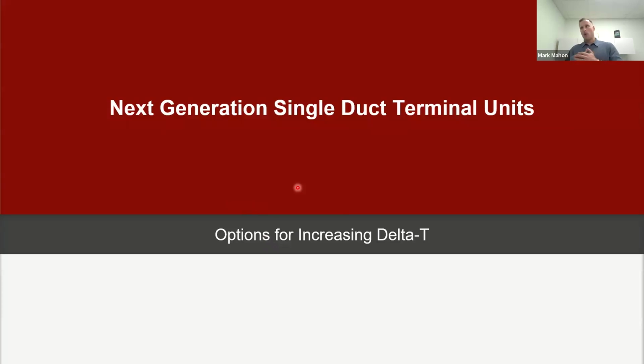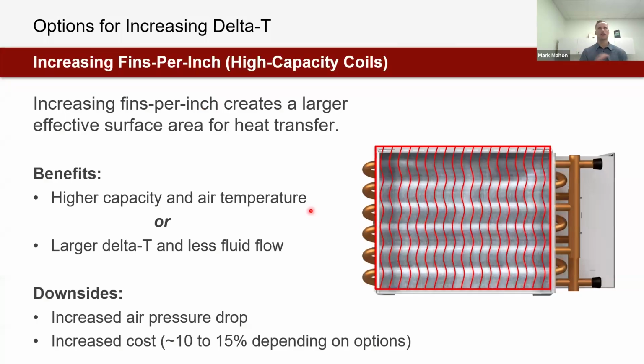So we've talked about why we need a lower return water temperature back to the boiler. But of course, when we think about the boiler's supply water temperature, that's not set by the single duct. That's set by the heating needs of the building. We're existing with 140 or with 120 or whatever it may be, and we want a lower return water. So that really means we need to increase the delta T to get a lower return water temperature. And I want to talk a little bit about how we can do that.